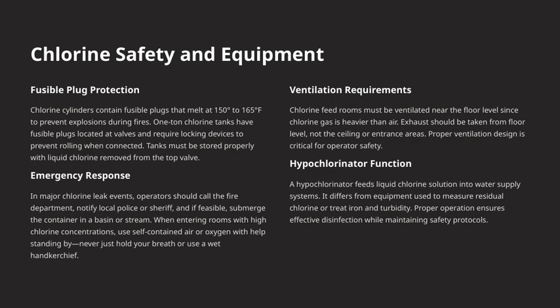Finally, let's touch on the hypochlorinator. This device feeds liquid chlorine solution into water systems for disinfection. It's different from equipment that measures residual chlorine or treats iron and turbidity. When operated correctly, it ensures effective disinfection while maintaining safety protocols. Understanding these safety features and procedures helps us protect ourselves and maintain safe operations when working with chlorine.